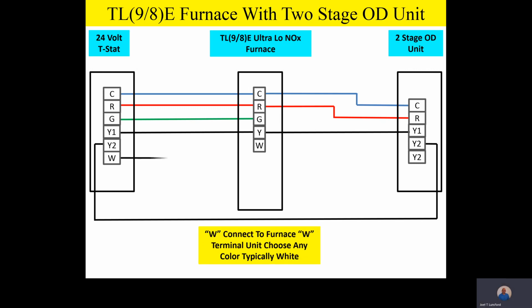Now, because this is a single-stage heating thermostat and a single-stage heating furnace, we're going to take W from the thermostat and connect it to W on the furnace for our heating call. And again, choose any color you like, but typically we find that most contractors will use a white wire for that heating call or that W call.